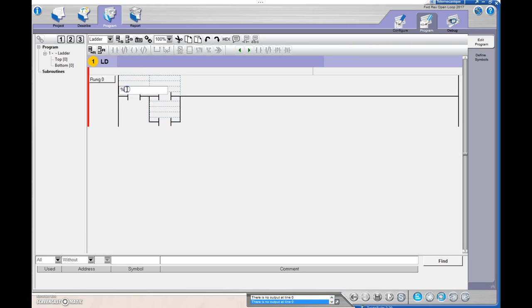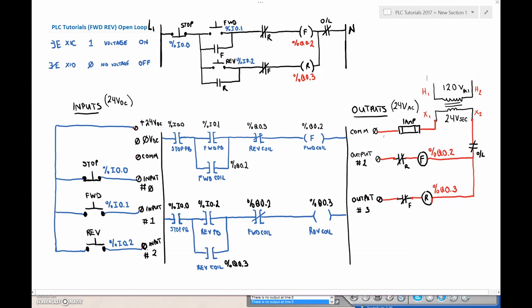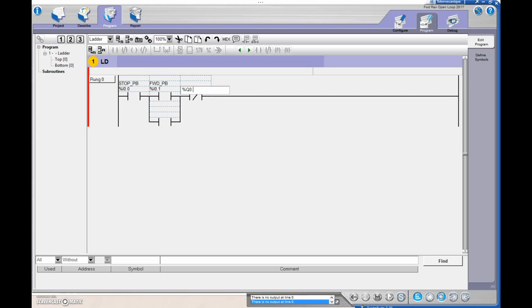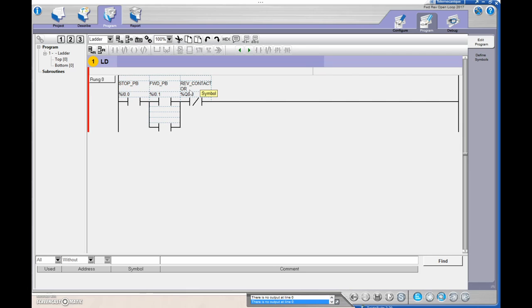For the stop, that's input 0.0. For the forward, it's %I0.1. Then the next thing I've got is my reverse coil, so %Q0.3. I'm going to drop in an Examine If Open at %Q0.3 — that comes up as my reverse contactor, confirming the reverse contactor is off. That means %Q0.2 is my forward contactor.